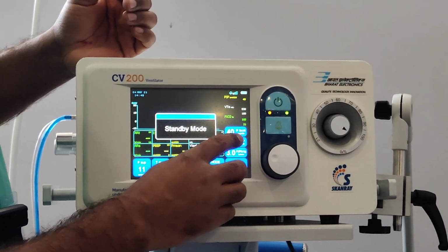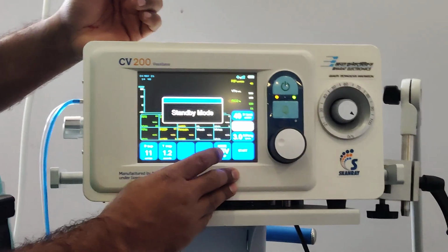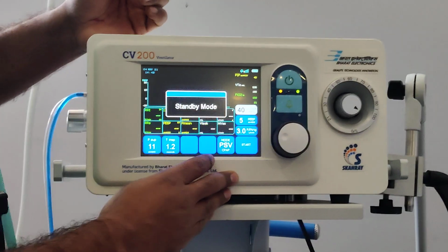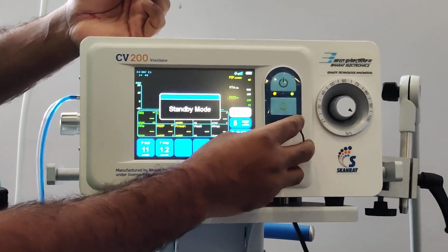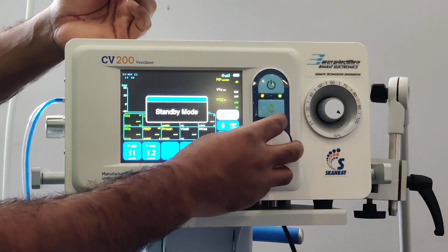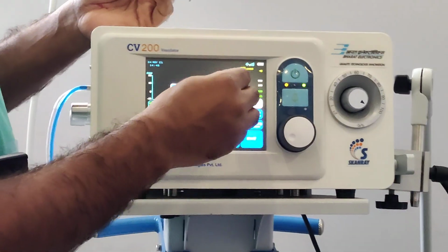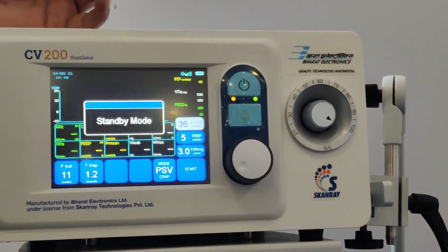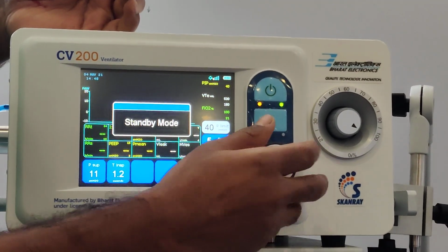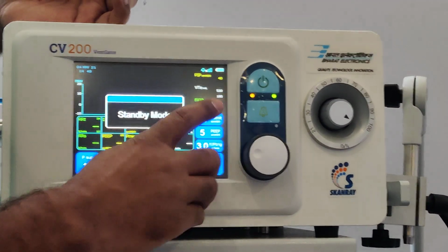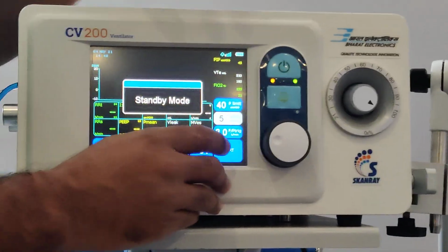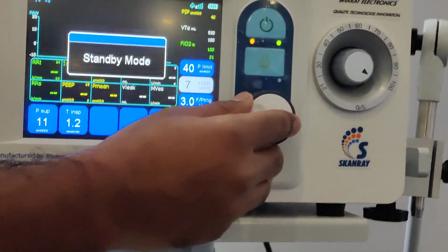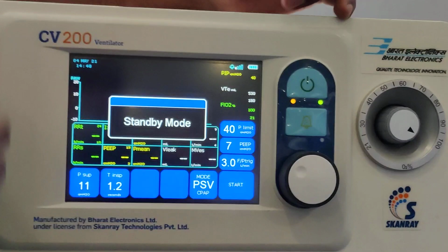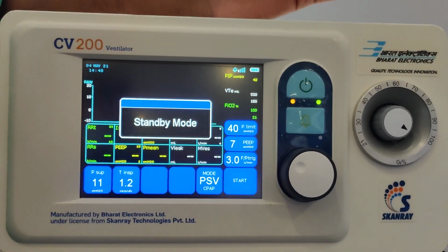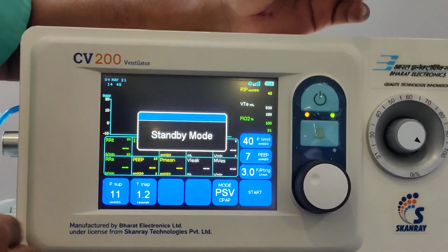Most commonly we start with some PEEP. The first button is pressure limit. This is usually fine with a 30 to 40 pressure limit. If you keep this pressure limit, the machine won't go above it and you can prevent injury to the lungs. Don't worry about this button, just leave it as it is. 40 is fine. For PEEP, usually we start with 5 or 7 for a patient. We don't want to start with a very high pressure, otherwise your patient won't keep the mask. So start with 7 of PEEP here.